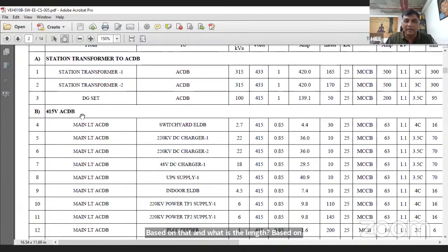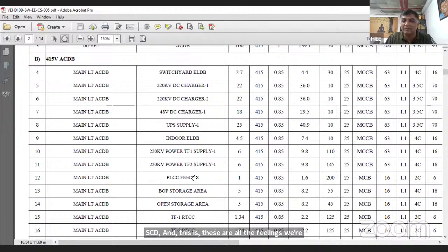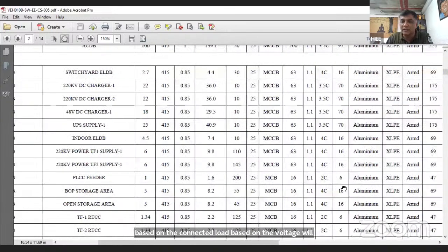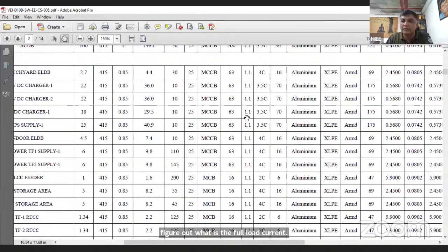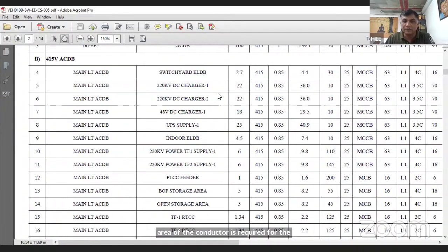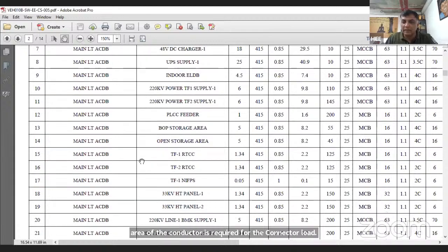So this is how. And from ACDB to all the outgoings, like I explained just now, main LT ACDB to switchyard ELDB, these are all the feeders we are connecting across ACDB, and this is the connected load. Based on the connected load and the voltage, we figure out the full load current. Based on that, we come out with what cross-section area of the conductor is required for the connected load. So this is the importance of cable sizing calculation.